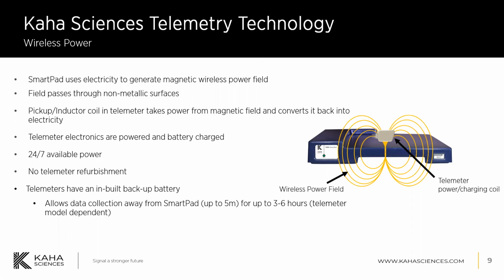So what this means is that you don't need to send them back to us between uses for the battery to be replaced. The battery can be recharged by the wireless power field. So there's no real lag time between experiments then. So you can take an explanted telemeter from an animal, clean it, sterilize it, and then put it back in an animal, and that can be done within 24 hours if really necessary.